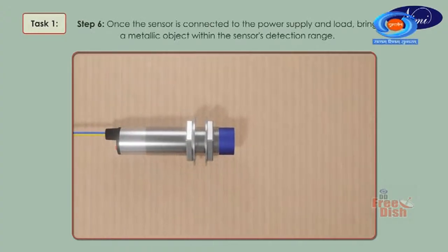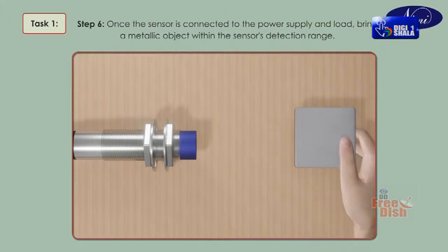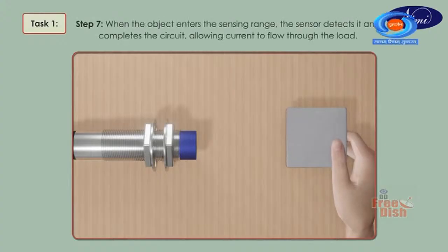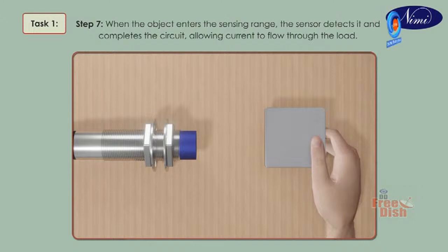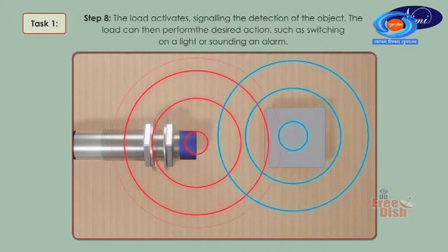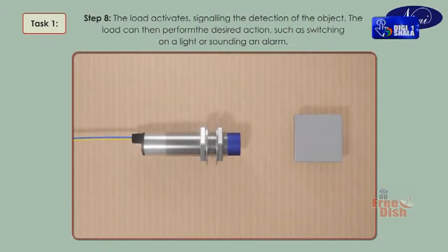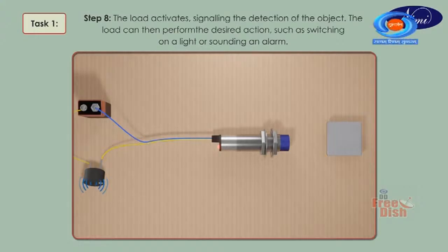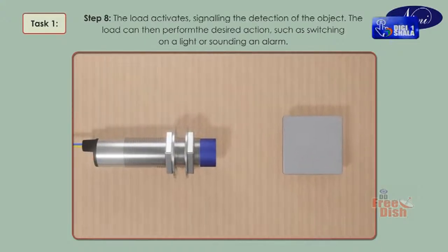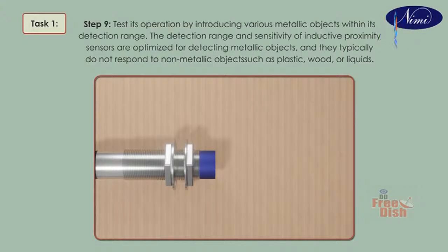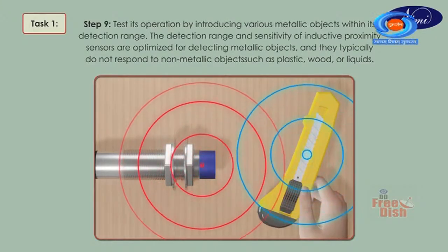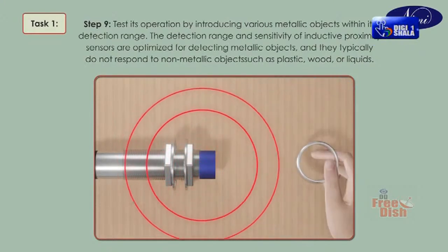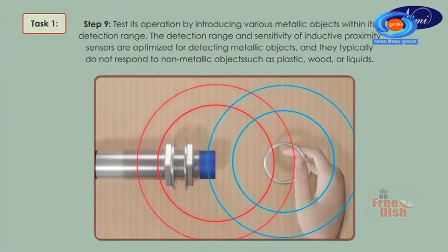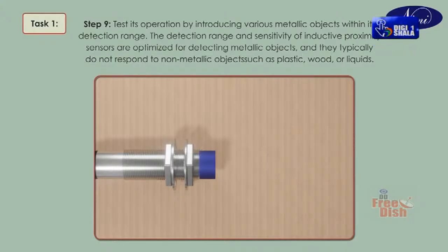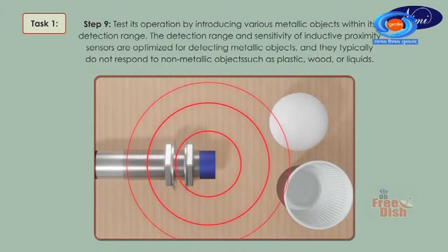Step 6. Once the sensor is connected to the power supply and load, bring a metallic object within the sensor's detection range. Step 7. When the object enters the sensing range, the sensor detects it and completes the circuit, allowing current to flow through the load. Step 8. The load activates, signaling the detection of the object. The load can then perform the desired action, such as switching on a light or sounding an alarm. Step 9. Test its operation by introducing various metallic objects within its detection range. The detection range and sensitivity of inductive proximity sensors are optimized for detecting metallic objects, and they typically do not respond to non-metallic objects such as plastic, wood, or liquids.